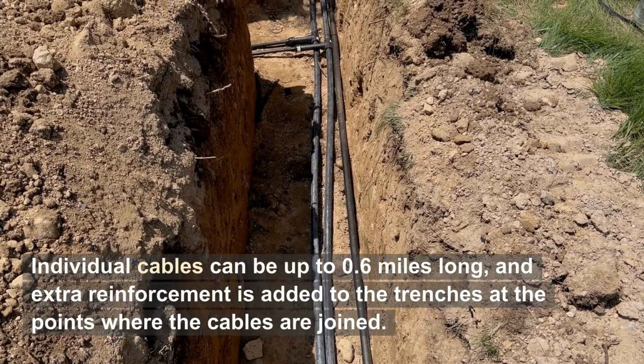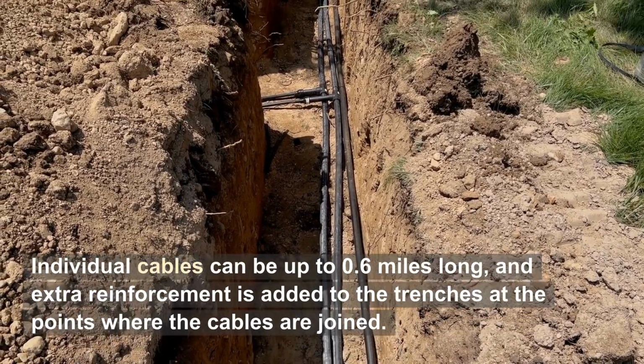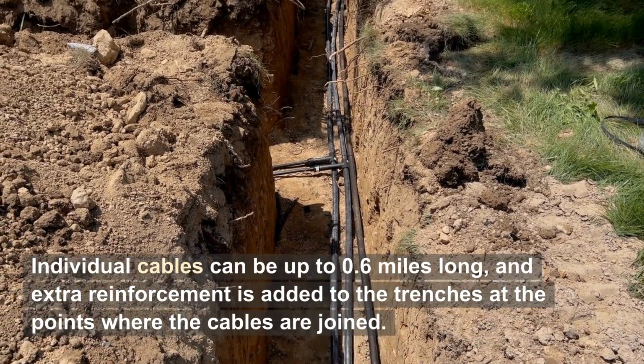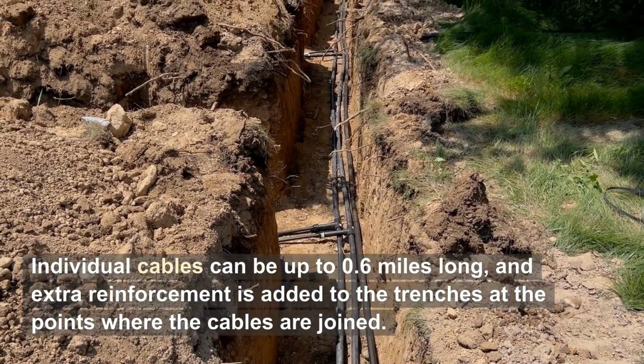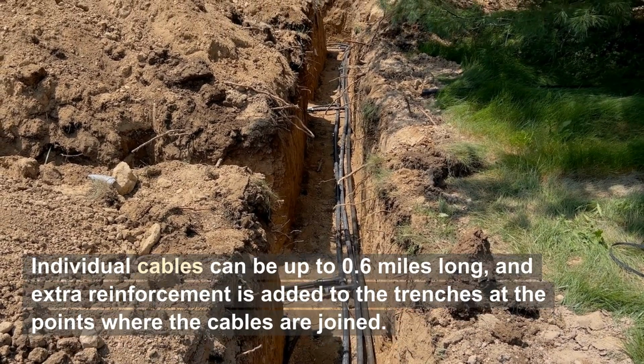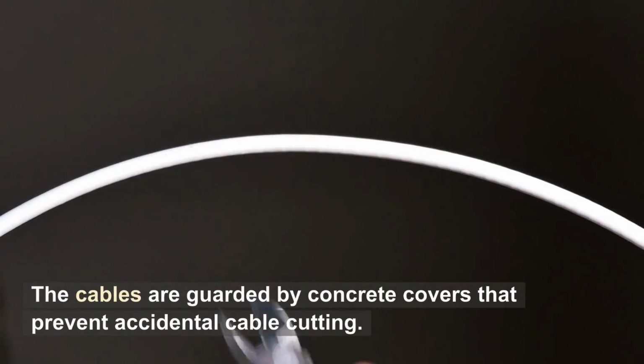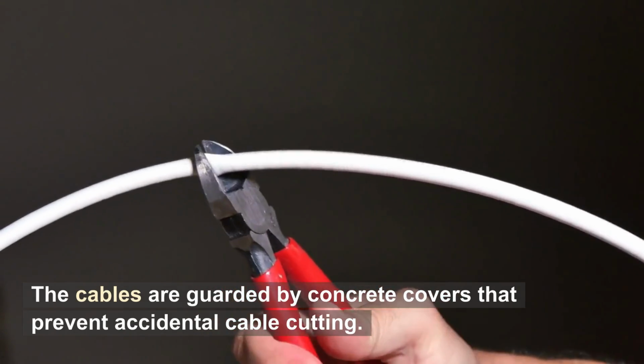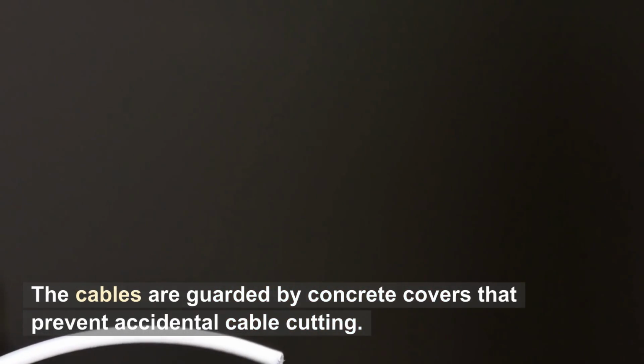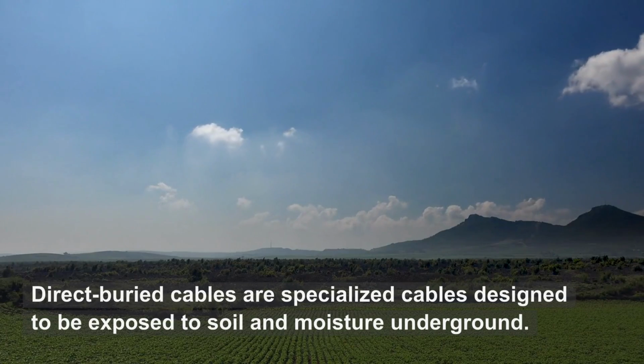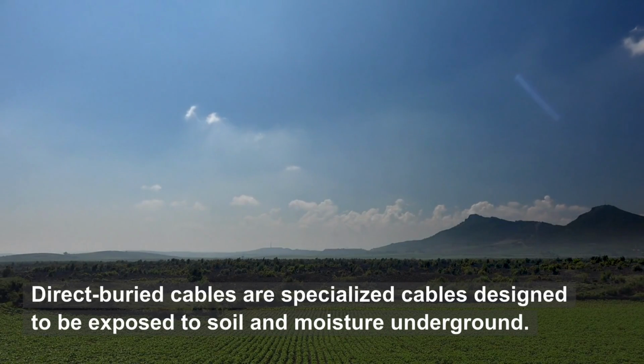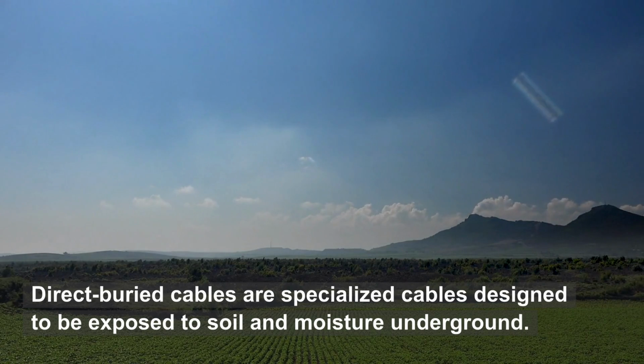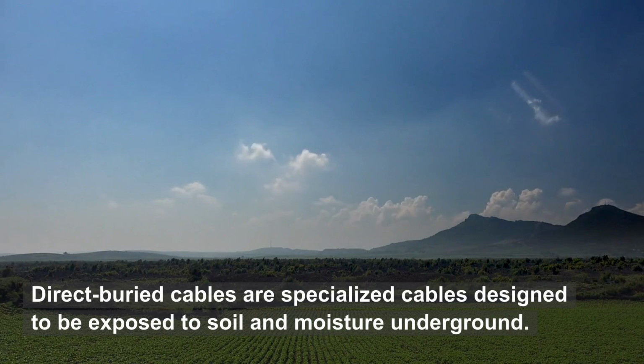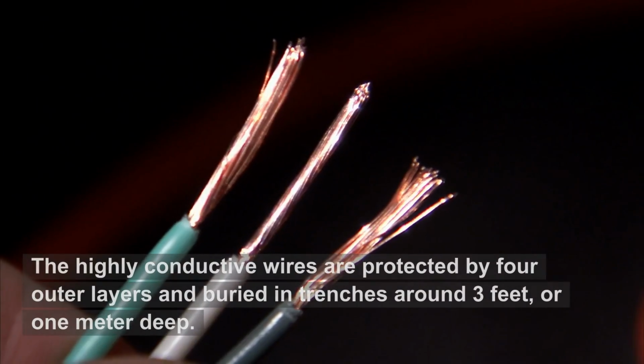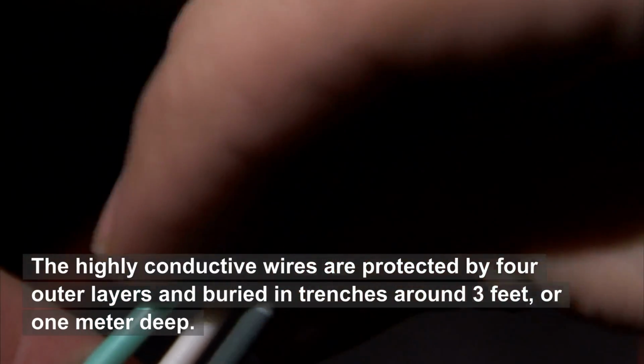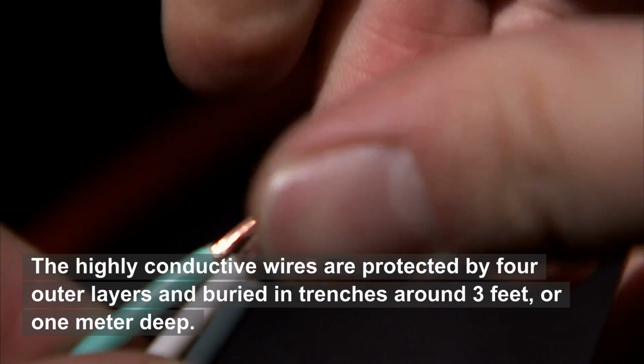Individual cables can be up to 0.6 miles long, and extra reinforcement is added to the trenches at the points where the cables are joined. The cables are guarded by concrete covers that prevent accidental cable cutting. Direct buried cables are specialized cables designed to be exposed to soil and moisture underground. The highly conductive wires are protected by 4 outer layers and buried in trenches around 3 feet, or 1 meter deep.